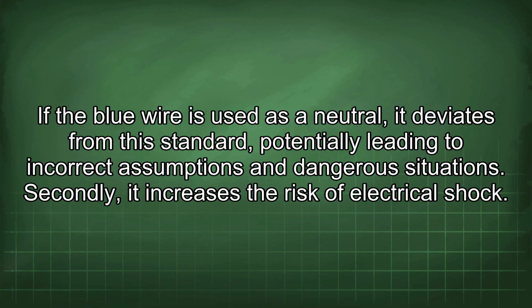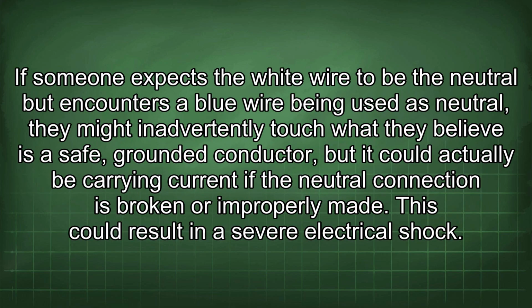and dangerous situations. Secondly, it increases the risk of electrical shock. If someone expects the white wire to be the neutral but encounters a blue wire being used as neutral, they might inadvertently touch what they believe is a safe, grounded conductor, but it could actually be carrying current if the neutral connection is broken or improperly made. This could result in a severe electrical shock.